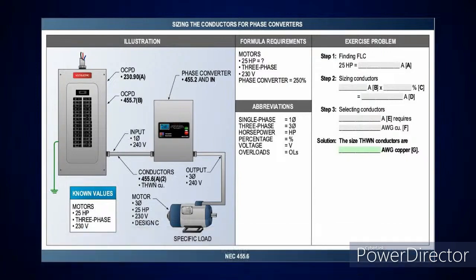To me personally, what I'm going to say on this, Raymond, is the way I look at that is that's a nominal voltage. So as long as you have a nominal anywhere from 230 to 208, the only time I've had issues with that is when you have a large demand. What happens is that 208 volts drops to like 196, below that manufacturer recommended voltage, and then that'll kill the motor. So you have to watch that.